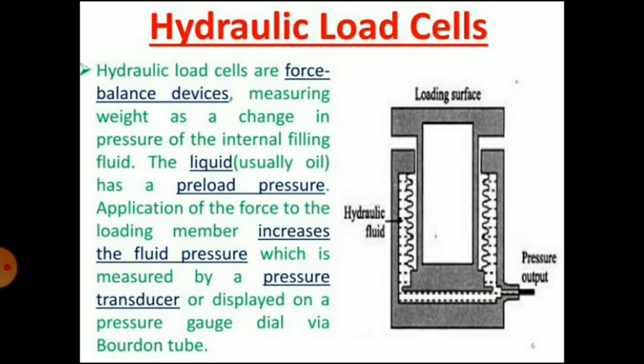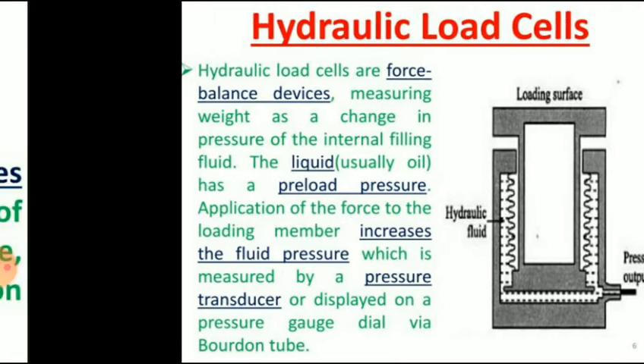The hydraulic load cells are force balance devices measuring weight as a change in pressure of the internal filling fluid. The liquid, usually oil, has a preload pressure. Application of the force to the loading member increases the fluid pressure, which is measured by a pressure transducer or displayed on a pressure gauge dial via a Bourdon tube. So this is regarding the hydraulic load cells.